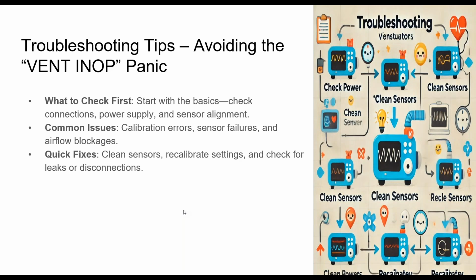But if you're using the wrong tubing, or if somebody's pushing the button and going into the extended self-test, and they really don't need to from a respiratory therapist standpoint, they could be calibrating the device against the wrong standard. Again, that gold standard tubing was very specific, at least specific enough to give a different level of compliance than standard tubing that one would typically see in an adult or pediatric setting.